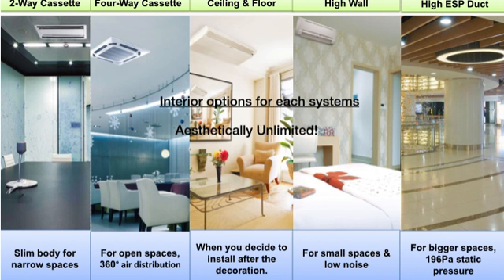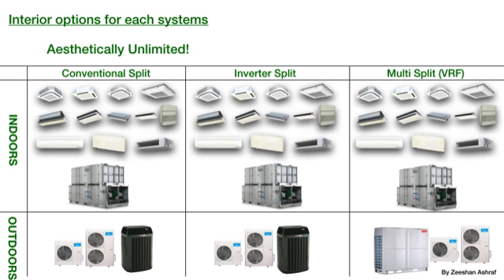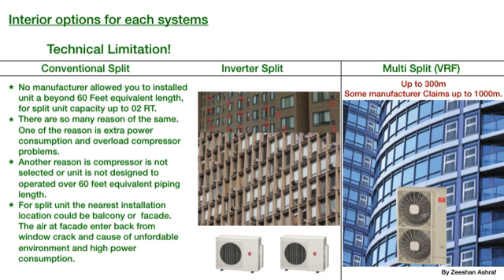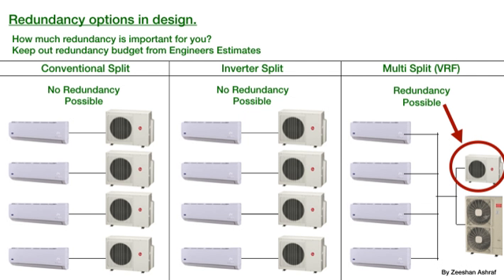Yes, for interior options of indoor units or air handlers, there is no limit on indoor units with each system. Some units are installed exposed, some remain hidden. The difference between their outdoor systems is energy consumption. Some indoor units have limitations. For example, a wall-mounted unit can't throw air up to 25 feet, and their outdoor unit has a limit of 60 feet of piping length between outdoor and indoor, as a long piping length causes higher pressure drop, extra compressor lift and extra amperage, therefore capacity decreases and maintenance cost increases.